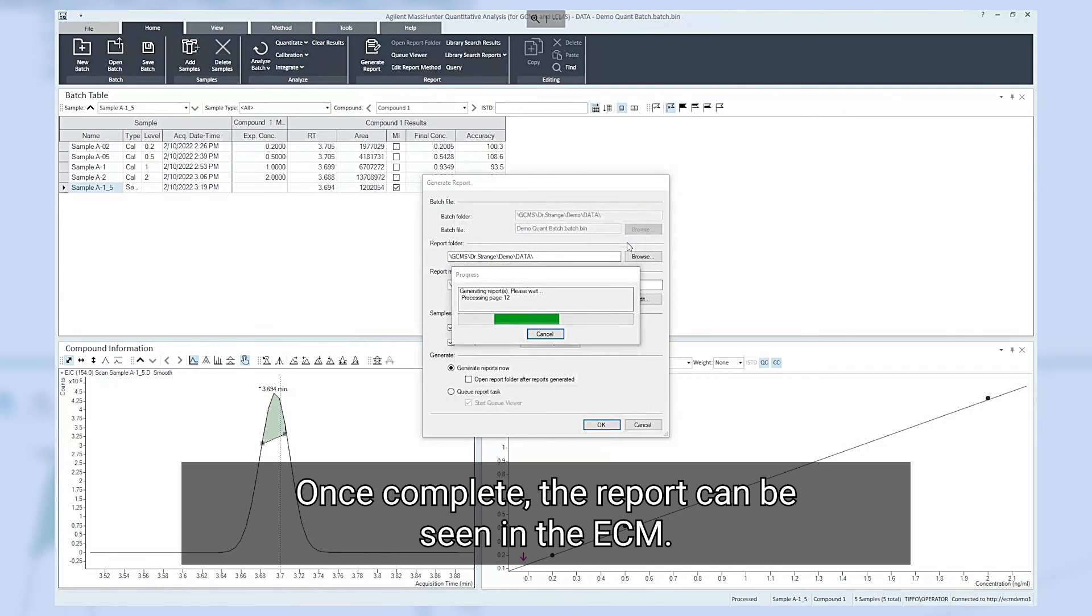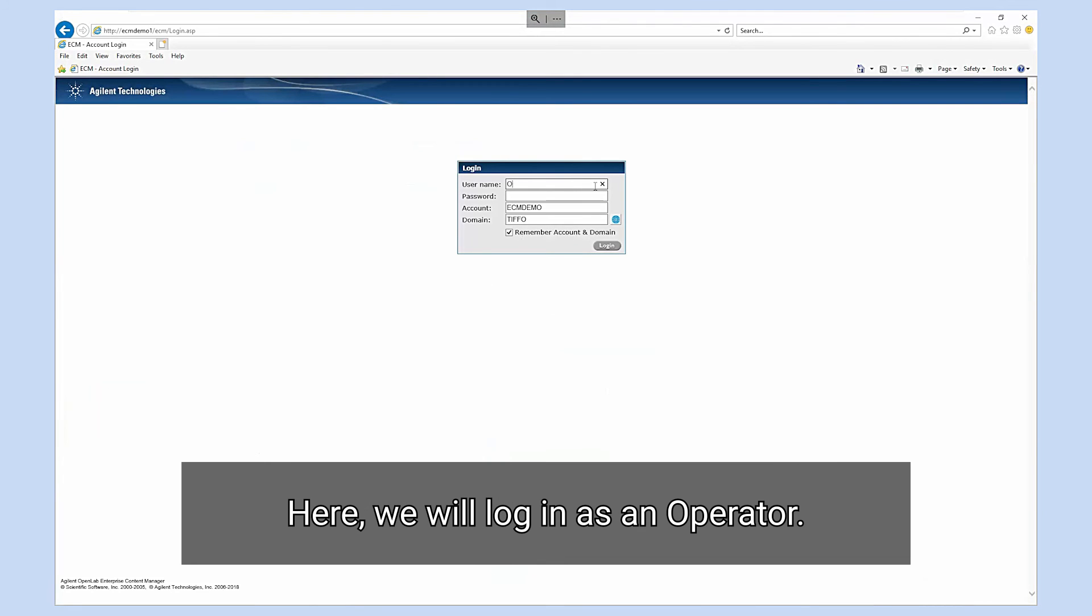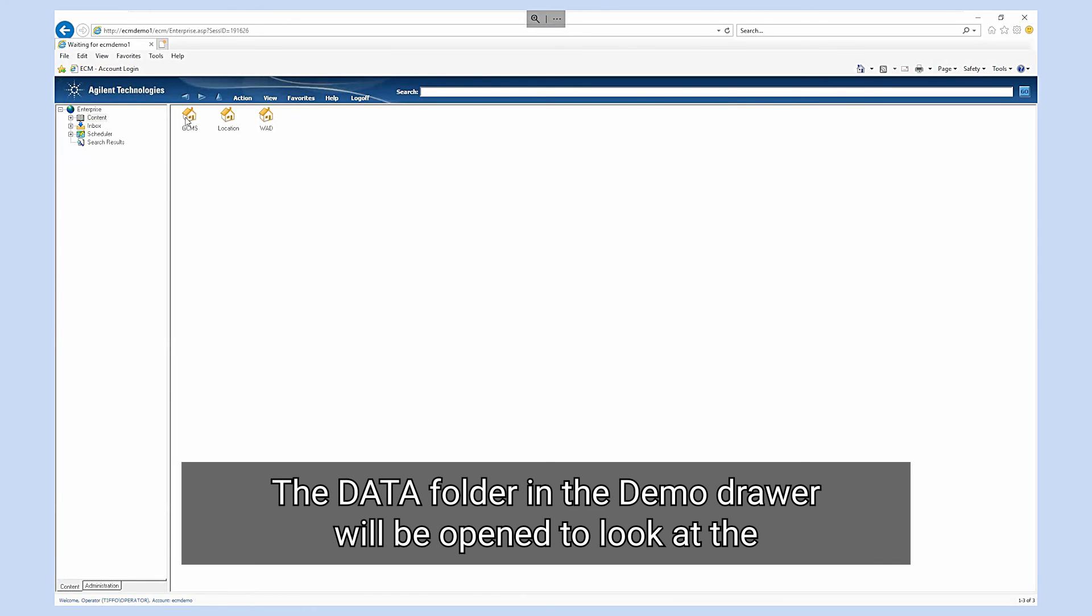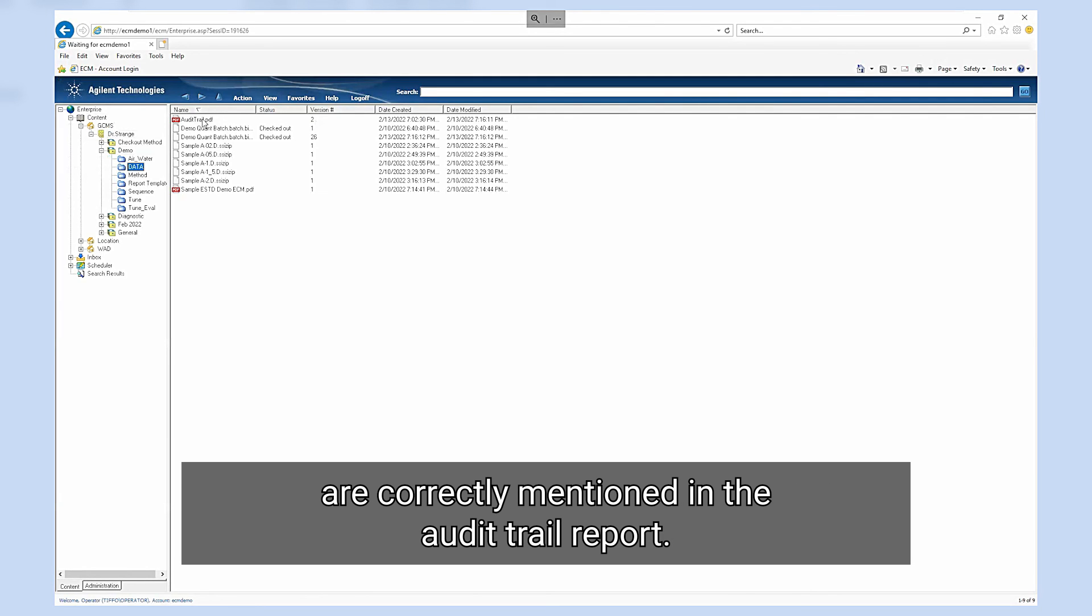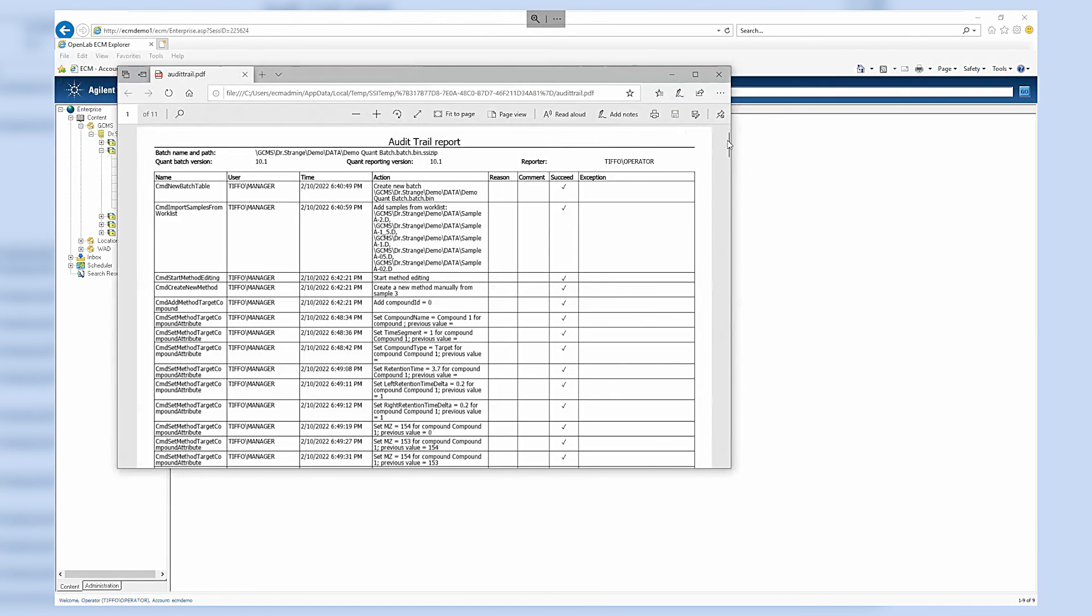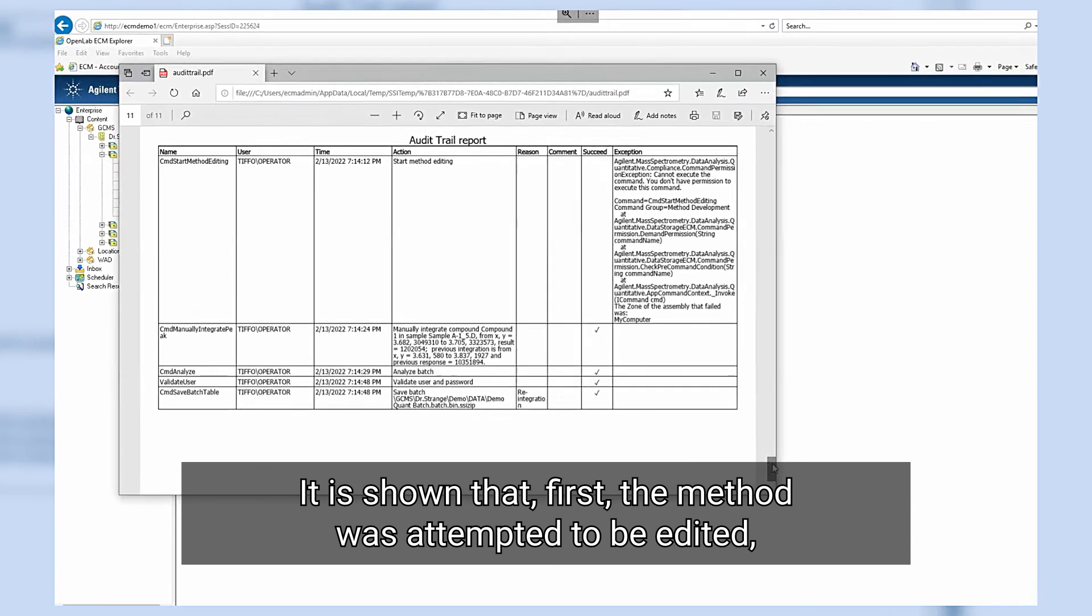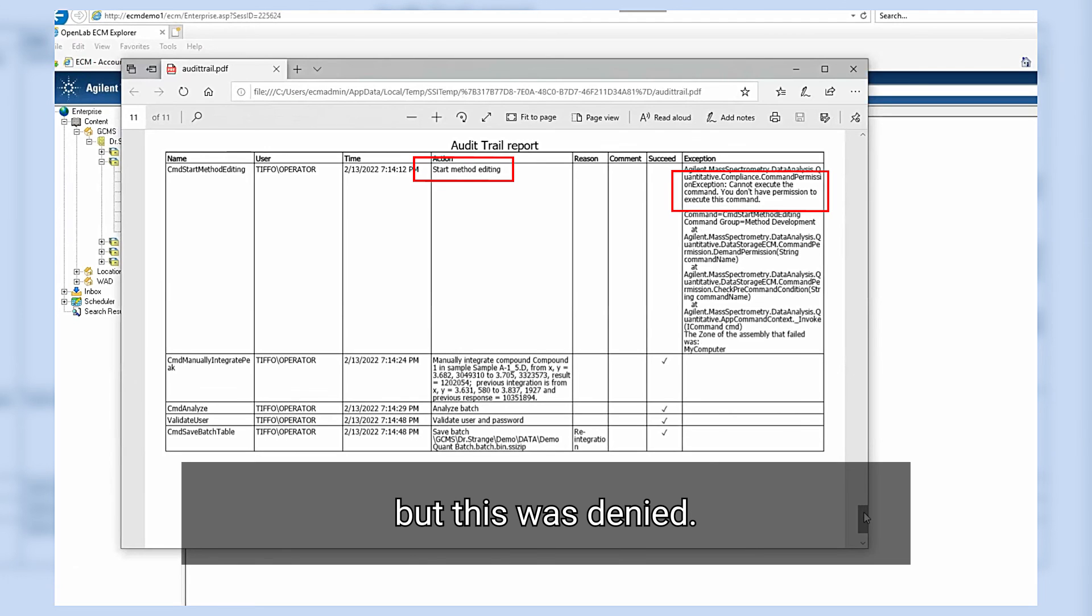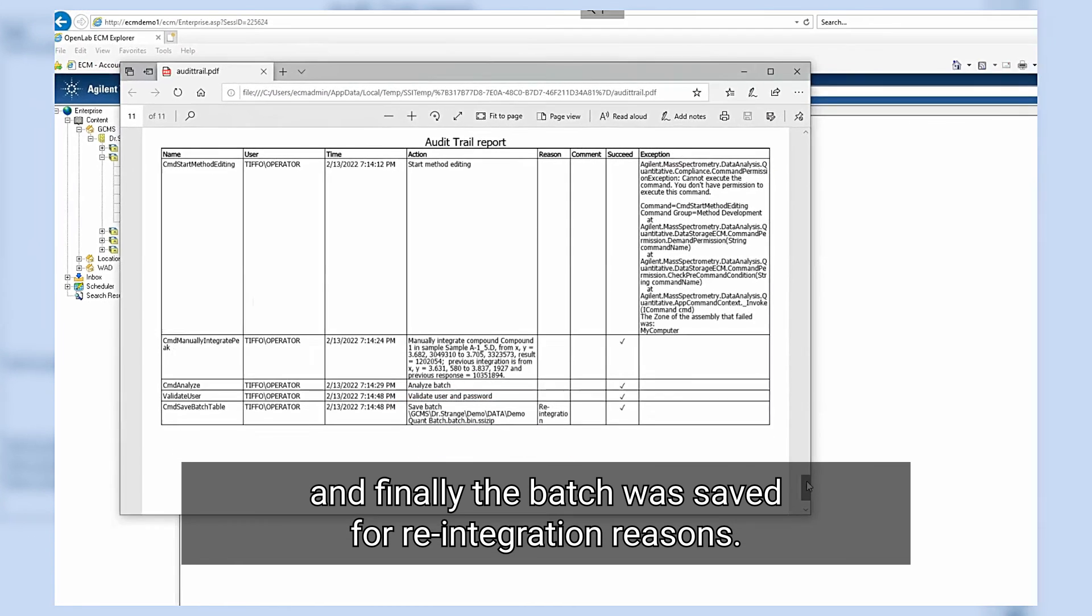Once complete the report can be seen in the ECM. We will look at this now. Here we will log in as an operator. The data folder in the demo drawer will be opened to look at the audit trail report and see if the actions performed in the software are correctly mentioned in the audit trail report. It is shown that first the method was attempted to be edited but this was denied. Then the reintegration was made and finally the batch was saved for reintegration reasons.